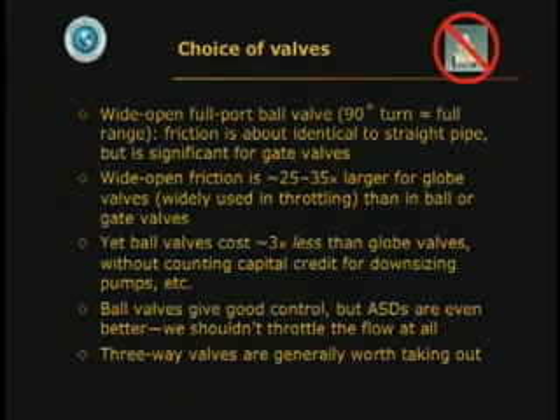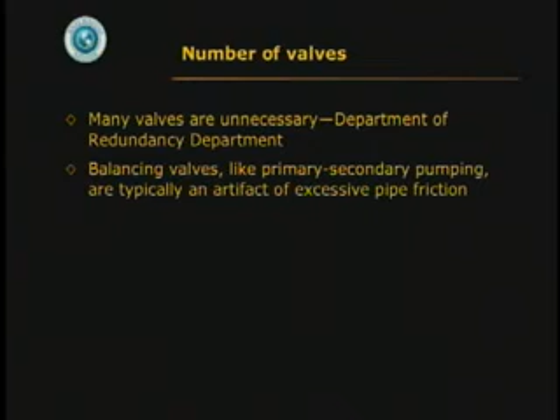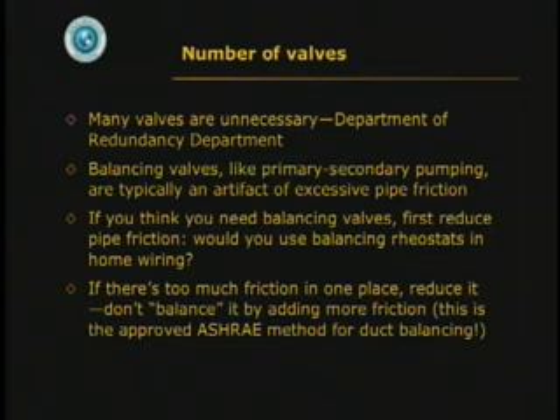There are a lot of redundant valves. There are a lot of balancing valves. Peter gave us an extraordinary case today of the enormous reduction in pumping power by not doing primary-secondary pumping at the Oakland airport. You know, would you put balancing rheostats in your home wiring to make the electrons go where they're supposed to? No, you make the wire fat enough that Kirchhoff does the work. Balancing valves, similarly, are an artifact of excessive pipe friction. And if there's too much friction in one place, reduce it. The ASHRAE method, if you have too much duct friction in one place, is to balance your duct flow by putting more friction in another place. You see something wrong with this idea?